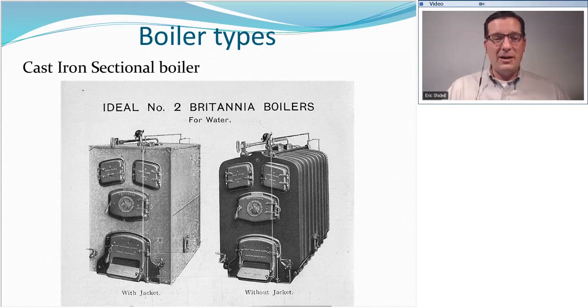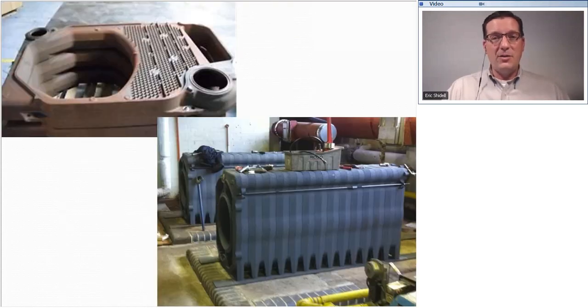Old technology. Here's some commercial sections. These are very large commercial cast iron boilers. Brand new one going in right here. And here you see all the different sections all lined up in a row. In this case, the burner is going to shoot in horizontally on this one. This could be either oil or gas. Don't know yet. Don't see the burner set up. These yellow pipes, maybe, I think it might be gas. And you can see the draw rod bolting the whole thing together.